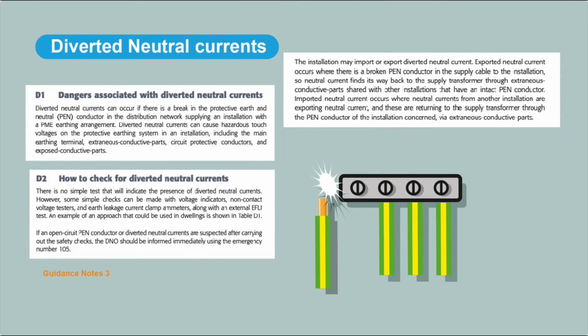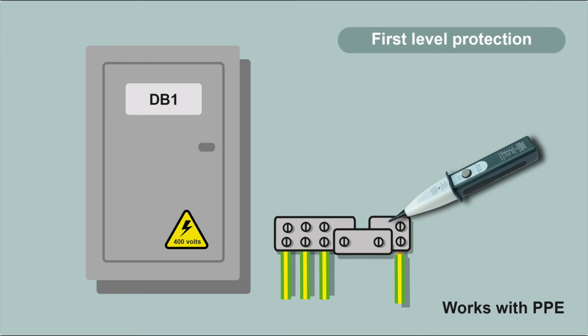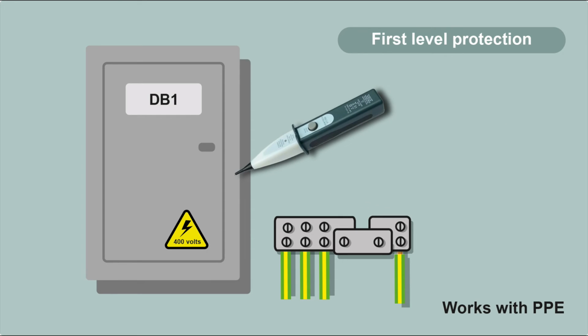I mentioned earlier that the pen type detectors do have a use in certain circumstances, and one of those circumstances is with diverted neutral currents, where hazardous touch voltage can appear on the protective earthing system and anything connected to it, which is basically everything. So we're not going to go into diverted neutral currents here. It's something that we all need to read up on and get familiar with. But these voltage pens can just give you your first level of protection. Say if you're approaching an MET or a distribution board, this pen can give you an indication that there might be an issue, there might be a voltage present. It's only an indication, and it's your first level.